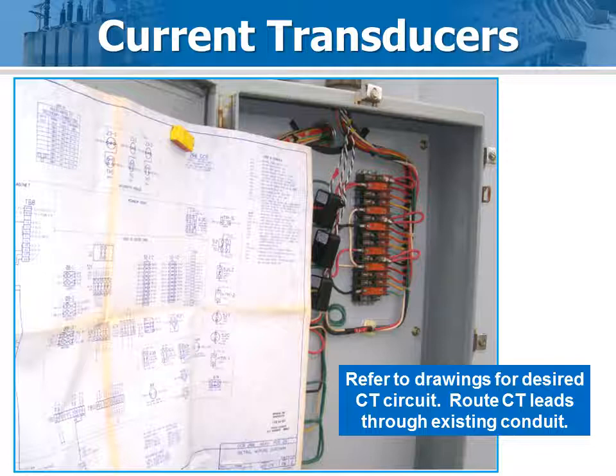For the SP, the CT circuits are located in a pull box on the left side exterior of the control cabinet. The twisted pair leads from the pickup coils can be fished through the existing conduit, cut to length, and connected to the CT inputs on the optimizer too.